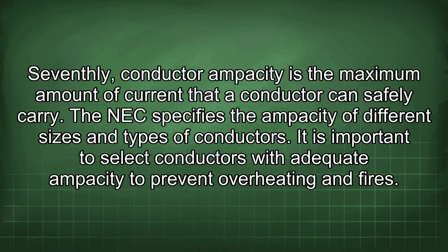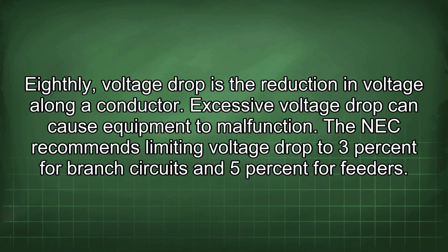The NEC specifies the ampacity of different sizes and types of conductors. It is important to select conductors with adequate ampacity to prevent overheating and fires. Eighthly, voltage drop is the reduction in voltage along a conductor. Excessive voltage drop can cause equipment to malfunction. The NEC recommends limiting voltage drop to 3% for branch circuits and 5% for feeders.